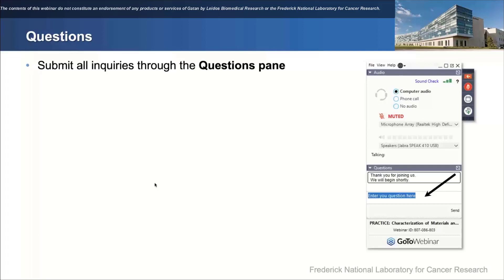What is the typical resolution that can be routinely achieved with the CryoArm and K3 in single particle? I think two angstroms is not out of the question — it's just a matter of sample prep. We haven't done beta-gal before at that level, but the only limitation I can see is the sample. The sky's the limit if the sample is done right, and you should be able to achieve 1.6 to 1.7 angstroms. Regarding Ewald sphere correction: for beta-gal we don't see much improvement at all, and for the ribosome we see a little more than 0.05 angstrom improvement — maybe 0.06 on average. This could be because Ewald sphere correction is not yet implemented in CTF refinement; that's something we'll be trying soon in the program M.